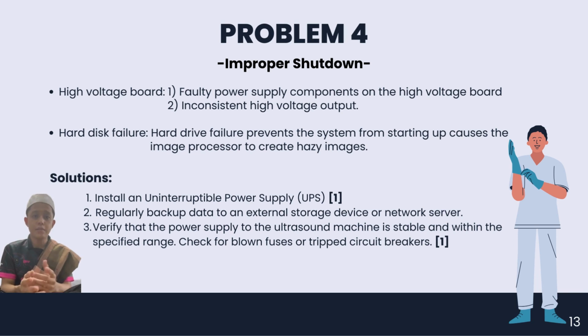Finally, verify that the power supply to the ultrasound machine is stable and within the specified range, and check for blown fuses or tripped circuit breakers. Normally, when there are blown fuses, there will be a short circuit.